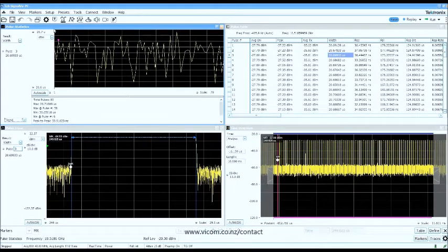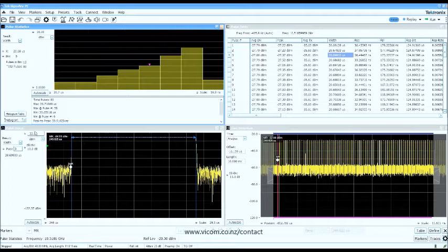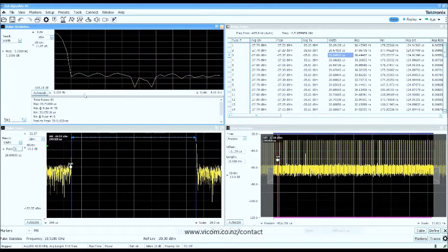The pulse statistics window can show you any column of measured data versus pulse number, or can show you a time trend to look for time varying characteristics in that measured parameter. It can also show you a histogram of that measured data, and even show you an FFT of any column of results. And that might help you find deterministic or parametric variations in a measured parameter.